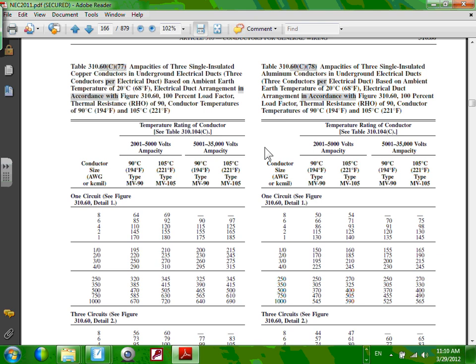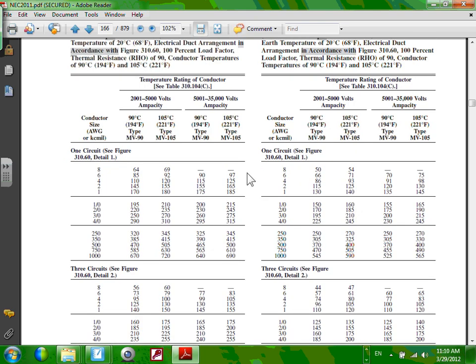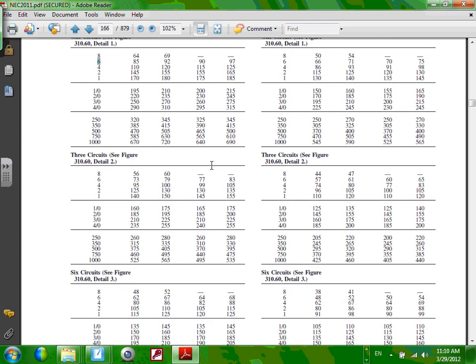All what you need to understand is, what was the voltage level that we have? You guys remember the voltage level that we had? Based on the detail, we're going to be using medium voltage 13.8. We have 13.8 and we're using 90, and the smallest conductor that we can use at this voltage is what number? Number 6.